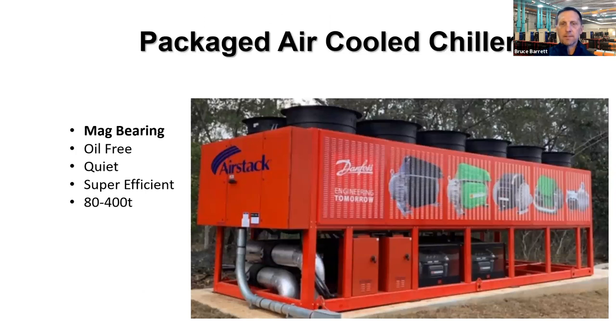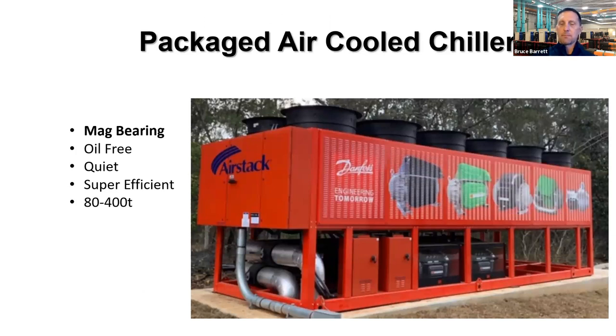All right, so some of this is a summary. I'm going to jump over from modular to package chillers. Our first seminar, we talked about mag bearing, oil-free, all those benefits, a system sustainability, having no oil in your system, all those parasitic loads, oil pumps, oil sumps, oil sensors, and oil itself damaging the long-term performance of your chiller as it sticks to the outside of the tubes and hinders heat transfer. Super quiet, super efficient, 80 to about 400 tons at ARI conditions.